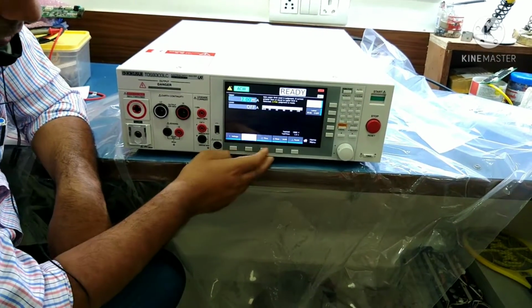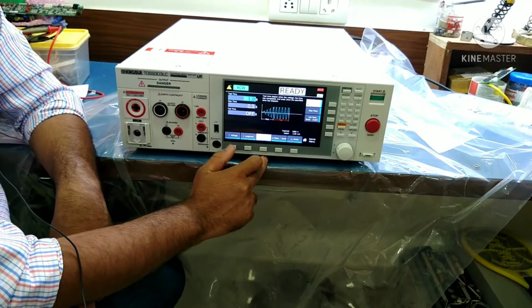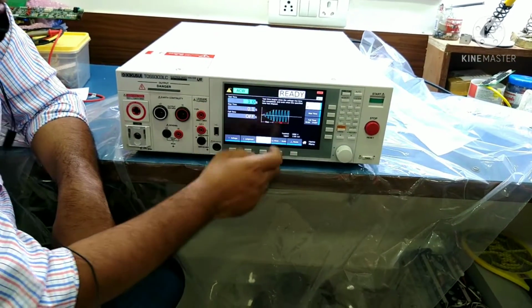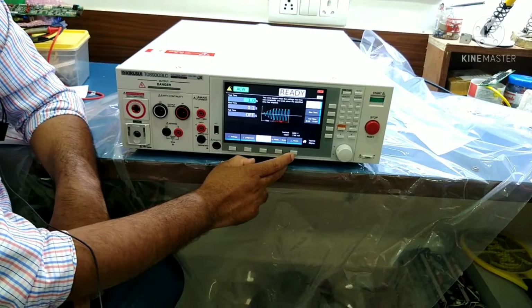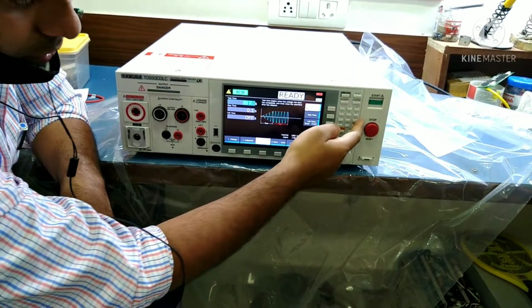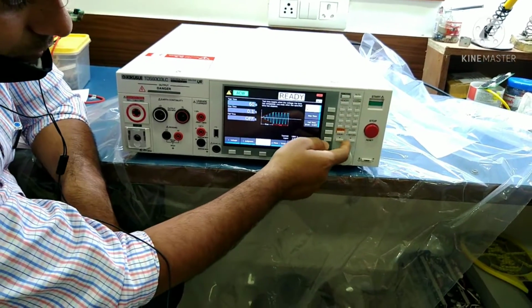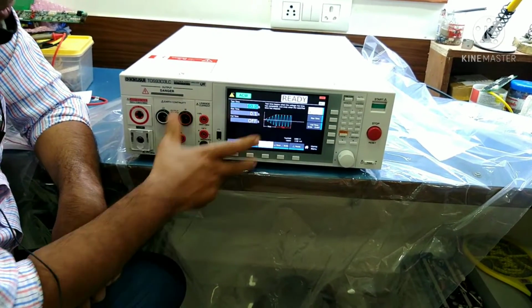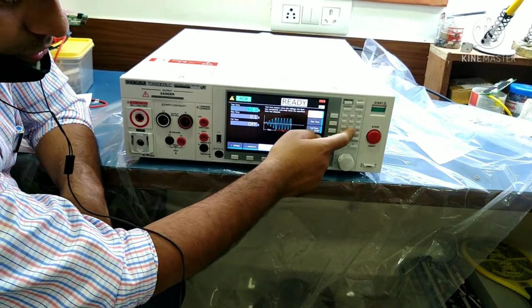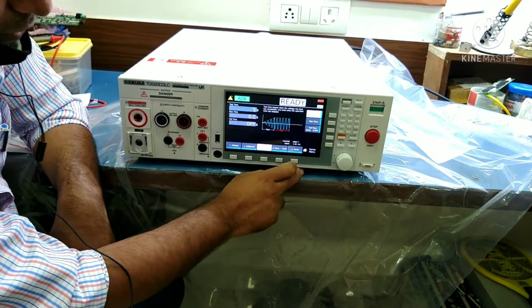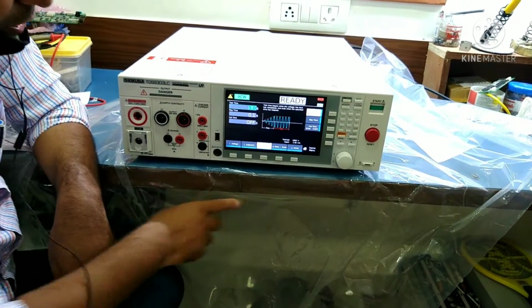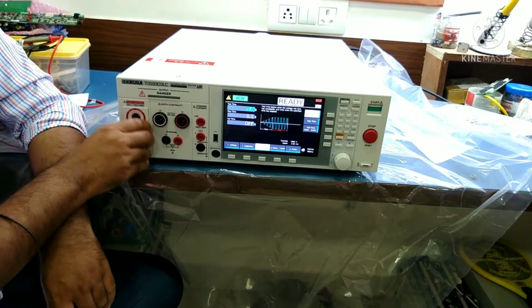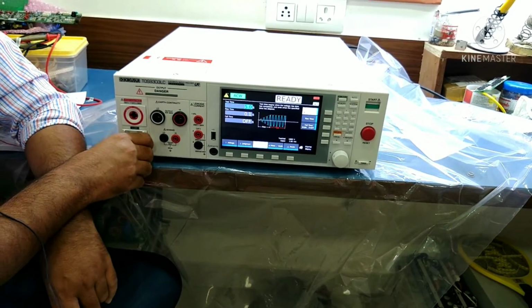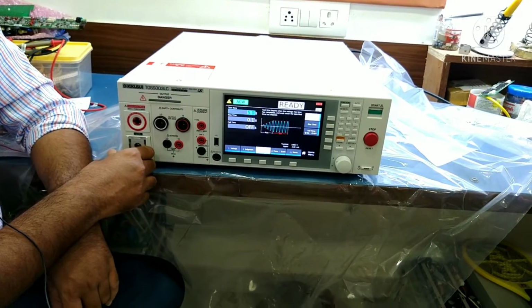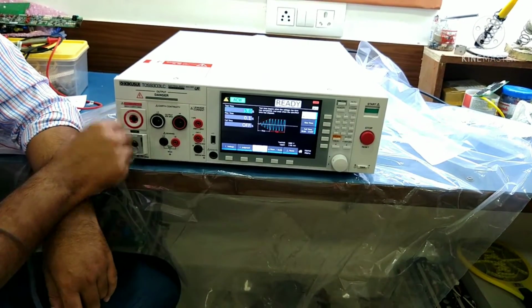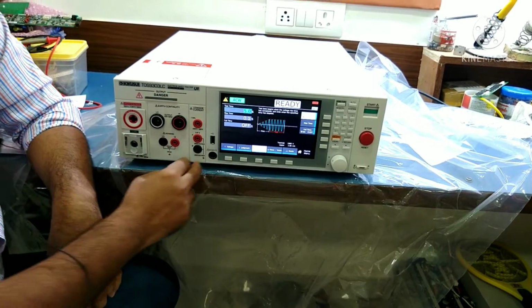Next is the timer, that is, for how long you want to run the ACW test. By default it is 1 second. You can make it 2 seconds, 3 seconds, whatever, up to 60 seconds, and the test will run for 60 seconds. Right now I am going to set only 5 seconds and press enter. Right now this is an open circuit and no device is connected. With an open circuit the judgment will be pass, because no current is flowing through the circuit, so it will show pass.